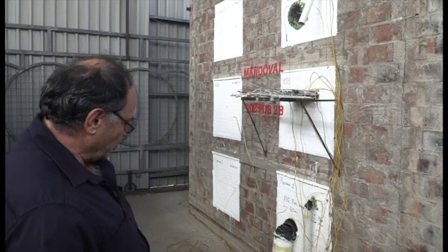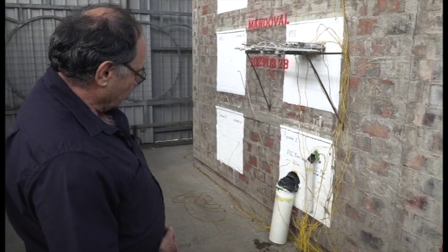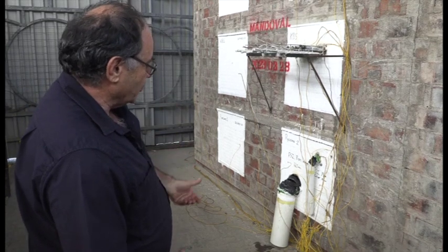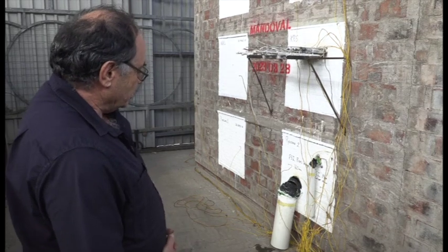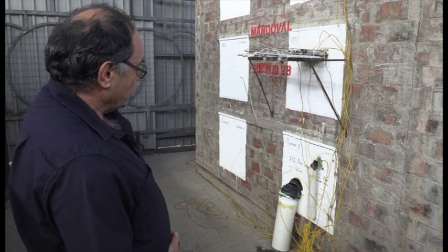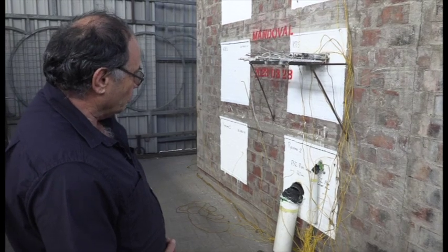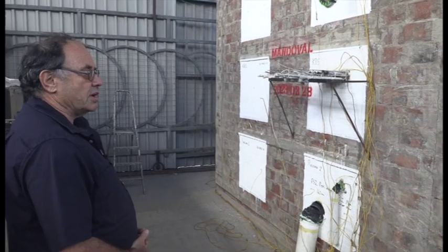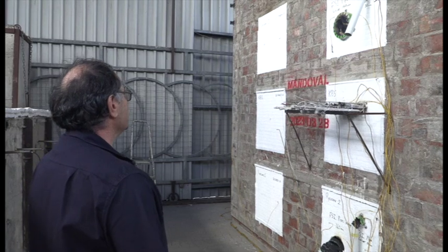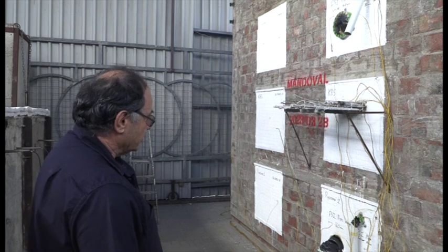If you look at the bottom there, I would say that is a bit of a harsh test for the pipe, because usually the pipe will be suspended on the other end as well, so that it doesn't fall off like that one. But let it be, it actually proves it's a better result than one would think, showing that the internal collar did also do its work by closing the gap completely. If you look at the temperatures that we achieved on the outside of these panels, they were all below 100 degrees Celsius for the blank panels and also the panels that had the pipes in.